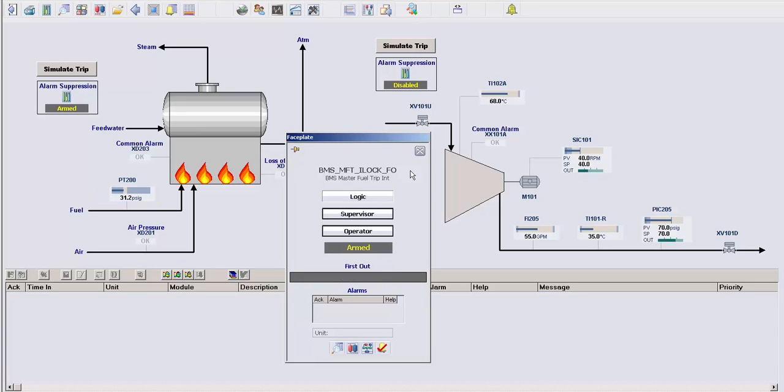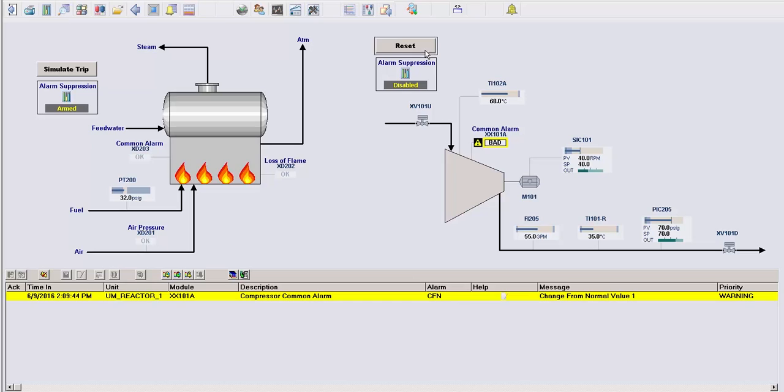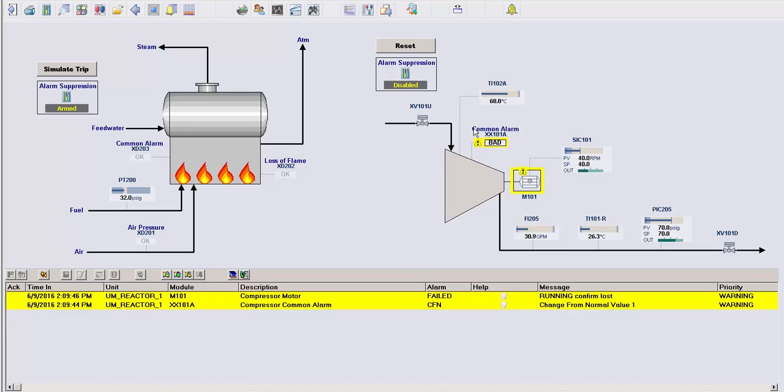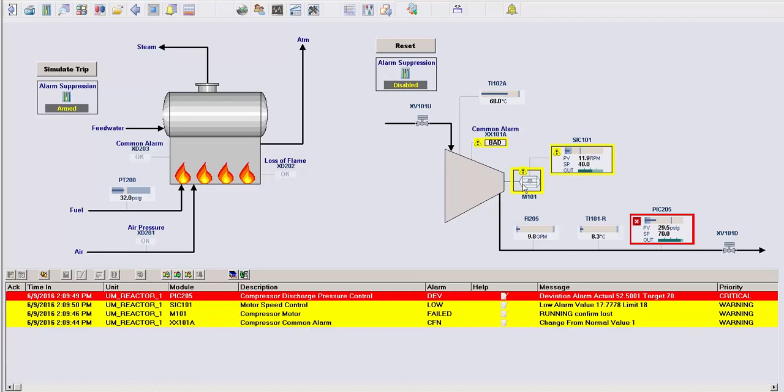Let me now show you the second variation of these alarm suppression modules, which has a few extra features. For this example, we're looking at a compressor that has several alarms associated with it. If I simulate a trip of this compressor, you can see how many alarms will eventually become active as a result of this, assuming these alarms have not been configured with some kind of conditions.